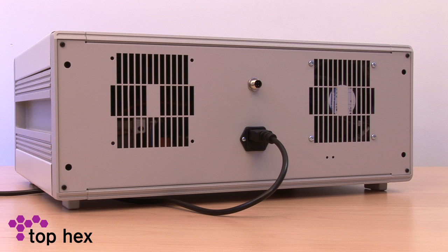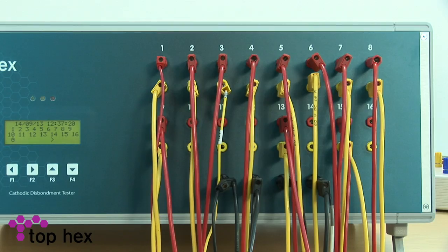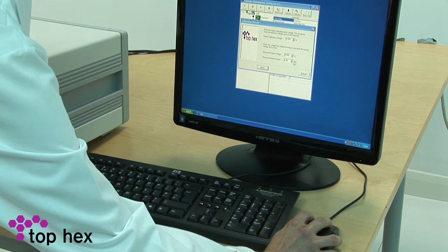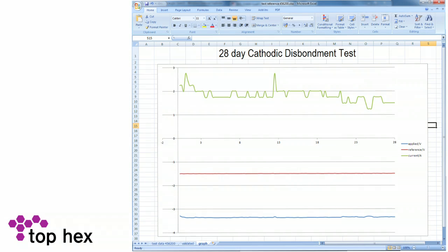The temperature logging module connects to the CD tester via a pluggable cable. During the test, the temperatures are logged to non-volatile RAM along with the CD test data. The test data can then be extracted onto your PC for analysis.